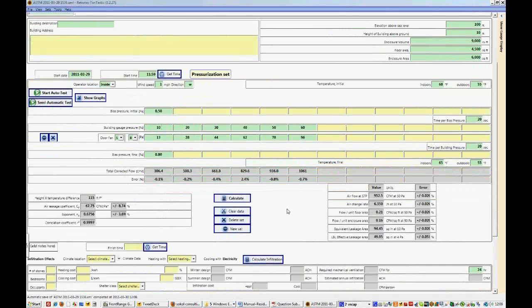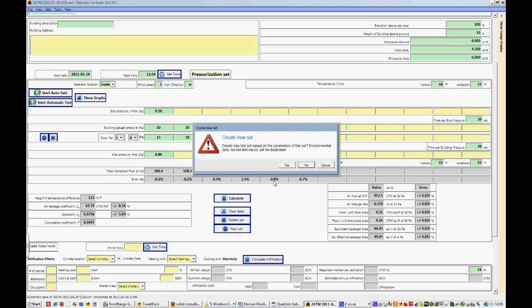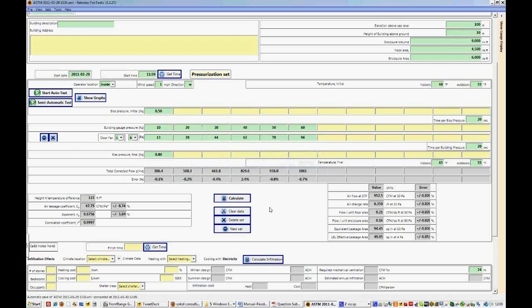So ASTM requires that you complete two tests, one in the pressurized direction and one in the depressurized direction. We can clear all the data in this test set, we can delete this test set, which we don't want to do, or we can add a new test set. So we're going to say new set. And yes, we want the set created based on the environmental parameters of the prior set. So we're going to say yes.